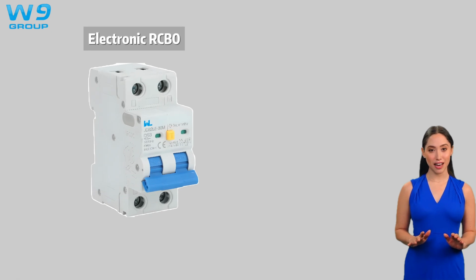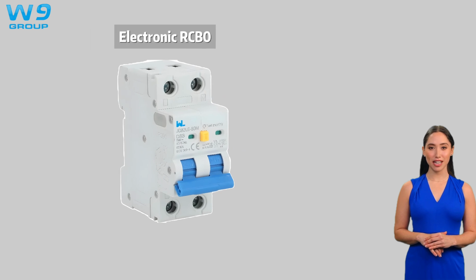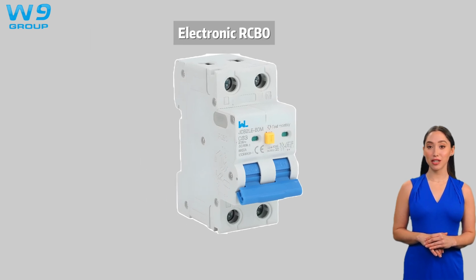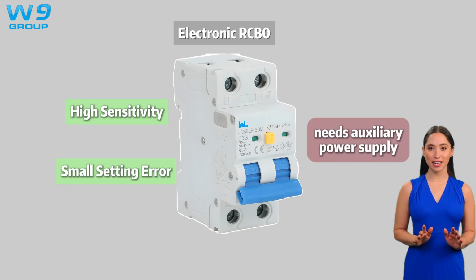When leakage occurs in electronic RCBO, the signal is transmitted to the relay after amplifier amplification, and the relay controls the switch to cut off the power supply. It has high sensitivity and small setting error, but it needs an auxiliary power supply.